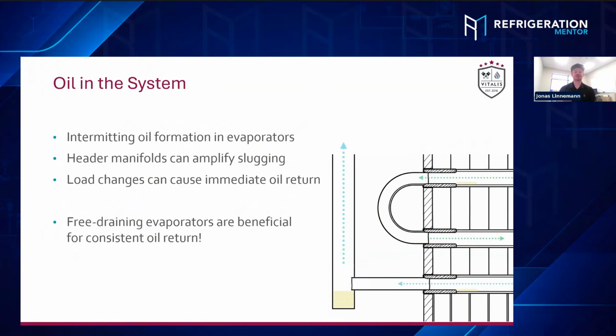So that's super important too, because you have to follow piping practices and look for slopes. Even though it's a new install, and it's been running for a few months, you've got to look up and look at the piping system and how it goes. I've actually seen, not on a CO₂ system, people pull soft copper and push it through the truss and just lay it right on the truss. Like there's a trap every 3 feet, or 5 feet. You can't do that stuff. So just look at it, because it'll give you a good idea. And a potential leak in the near future, because it's grinding off from these trusses, right?